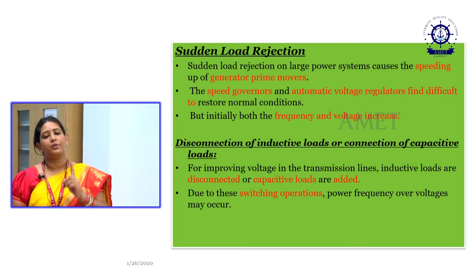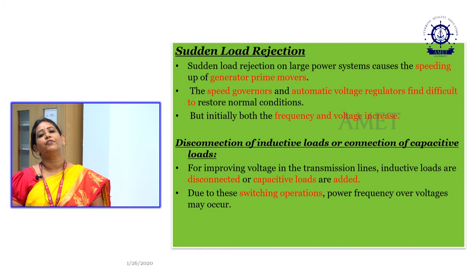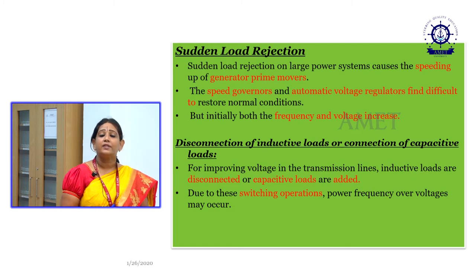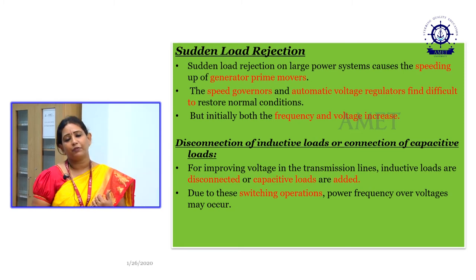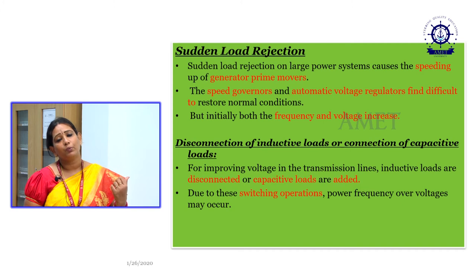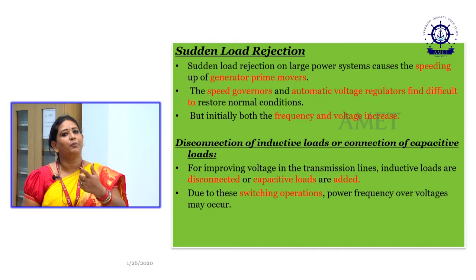These overvoltages pertain to a single frequency. For the Indian system it is 50 hertz, and for other countries it is 60 hertz. But the voltage value is going to be high, unlike the previous switching overvoltages, where the voltage is high and the frequency is also very high, greater than 500 kilohertz. Here the frequency is 50 hertz, the power frequency, but the voltage is going to be very high.